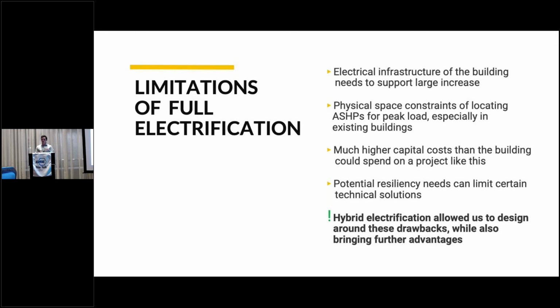And so there was a capital impact where the capital cost tripled just for the equipment cost, and additionally the physical space required for these heat pumps tripled, which was no longer viable with the given roof that we were dealing with. All of those two things combined, plus the fact that when you're fully electric, a new issue comes into play where you have no resiliency if the grid goes down. We get another Hurricane Sandy or any natural disaster where the grid goes down, we're out of luck. And so those things combined made a full electrification project very difficult to, in good faith, recommend.